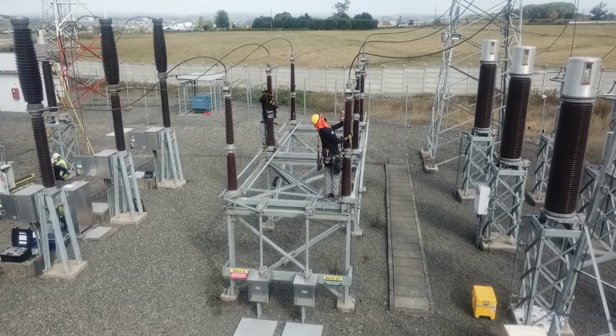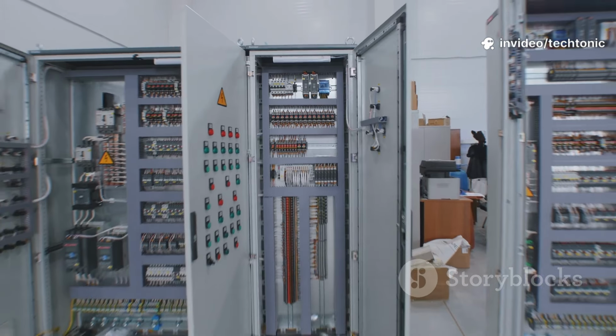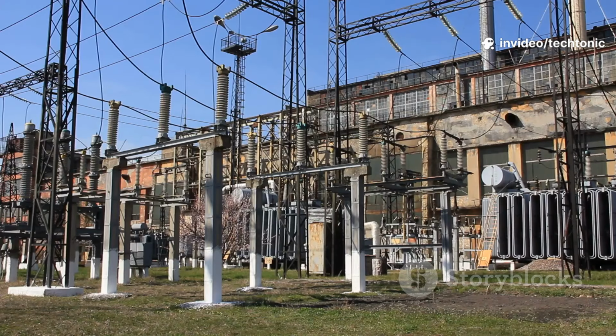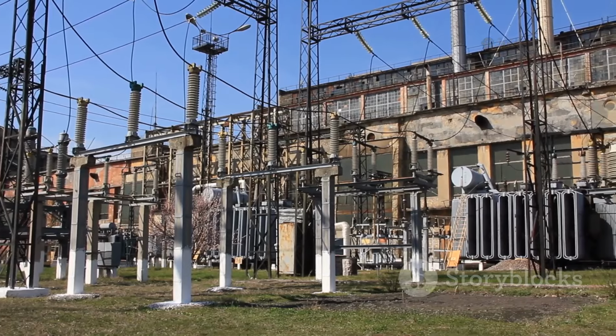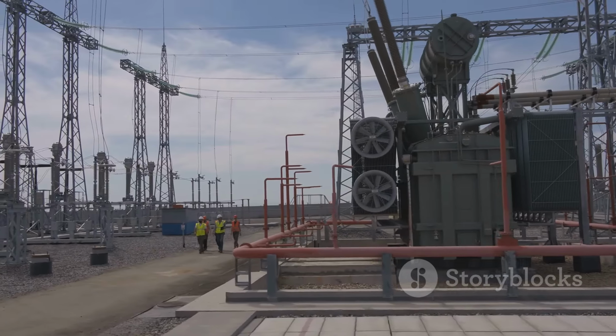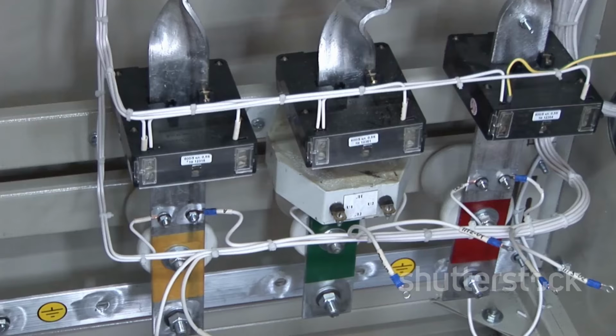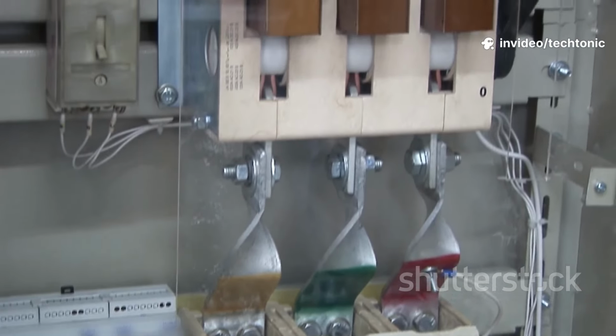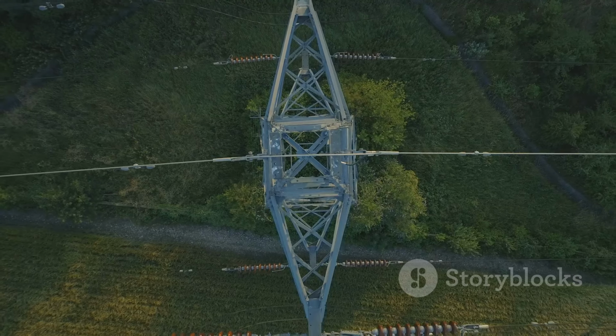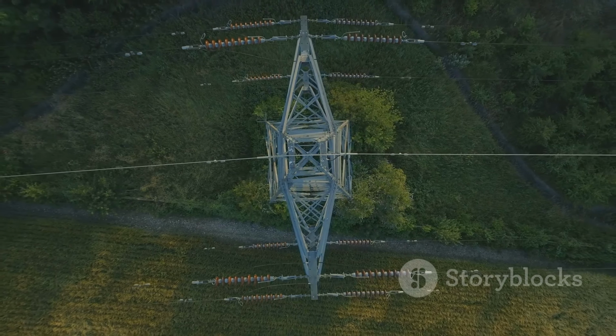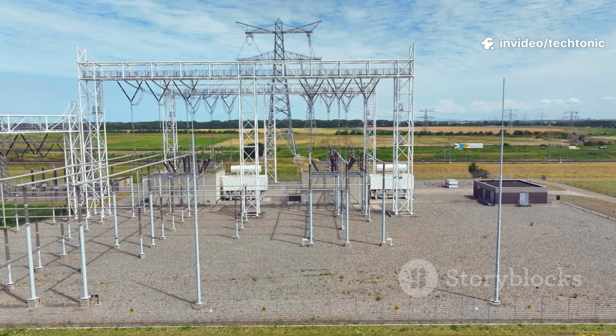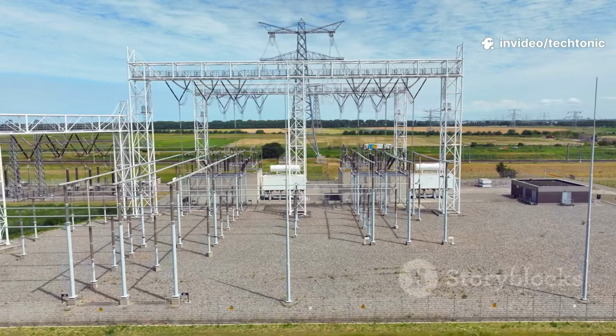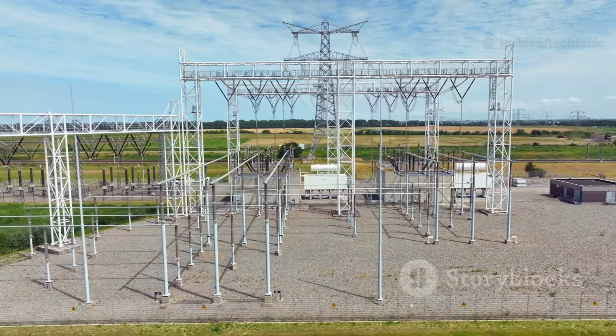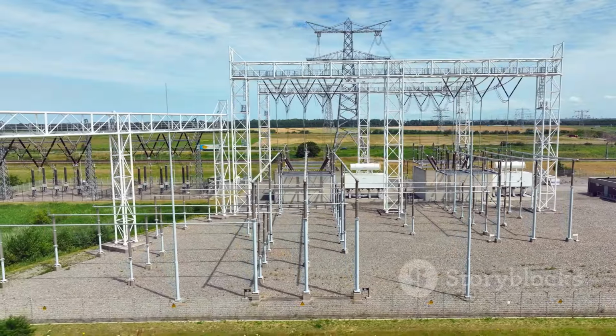Of course, there's a catch. Our power grids generate and use AC power, so to use HVDC for transmission, we need to perform a bit of electrical alchemy. This happens inside massive buildings called converter stations. At the sending end, high-voltage AC from the grid is fed into the station where powerful electronic switches, like thyristors or modern IGBTs, convert it into DC. The electricity then travels along the HVDC line. At the receiving end, another converter station, called an inverter station, does the exact opposite. It takes the high-voltage DC and converts it back into AC, ready to be integrated into the local grid and sent to consumers.